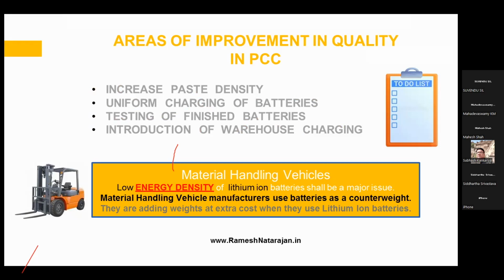What one has to do is make some changes in the manufacture. Another thing is uniform charging of batteries becomes very important in the case of cycling batteries, because a difference in cell specific gravities, and thereby cell voltages, creates problems, especially at low voltage. That is why depth of discharge has to be controlled to maybe 65, 70, or 75 percent, and you shouldn't even go to 80 percent depth of discharge. If that can be done, 70 percent would probably be safe, and we may not have much problem with lead acid batteries used for cycling application.